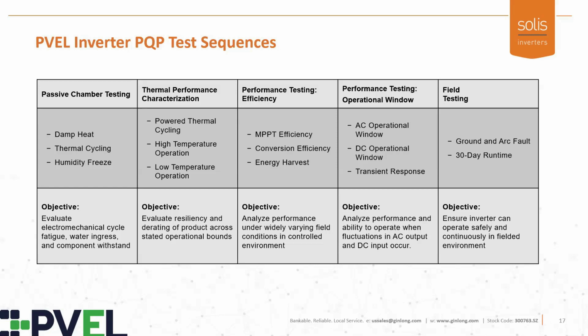Similarly, for powered thermal cycling, we are operating the units from their minimum nameplate to their maximum nameplate ambient temperature and inside of their DC and AC capacities. But we're trying to push these products such that they are stressed in a fashion that could occur in the field, such that we can get faster accelerated turnaround lifetime data for each of these individual products. That includes high temperature operation, which is many times called dry heat, and low temperature operation as well.